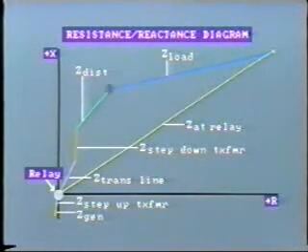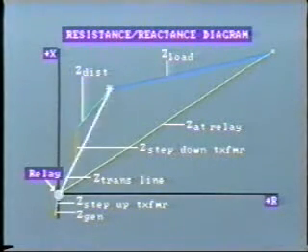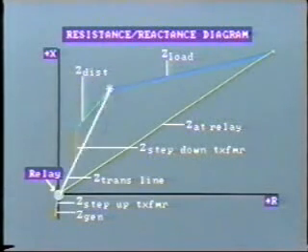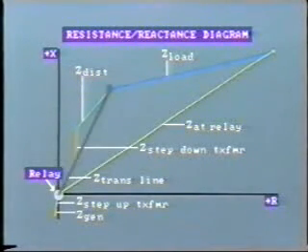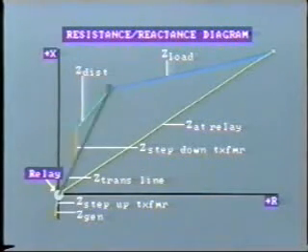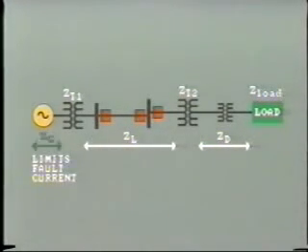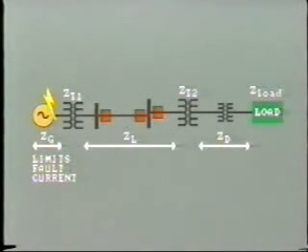If we have a short circuit close to the load, you can see that there will be a dramatic decrease in impedance, but its phase angle will increase considerably. As the fault becomes closer to the source, the impedance is much less and consequently the fault current will be much higher. It is important to remember that the generator itself contains impedance, which serves to limit the magnitude of fault current even for a short circuit on the generator terminals. Of course, the short must be cleared quickly to avoid serious damage.